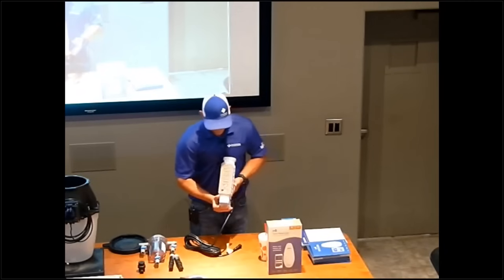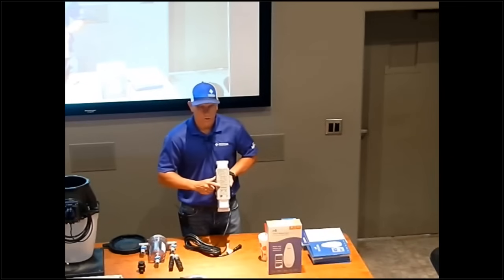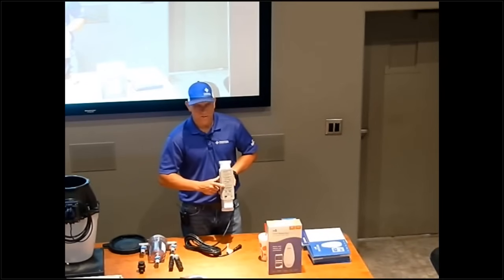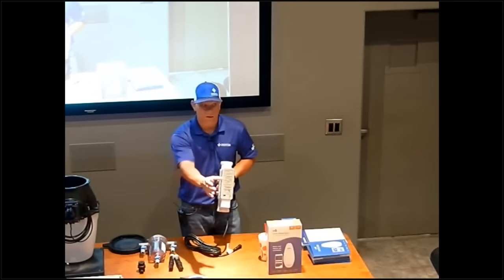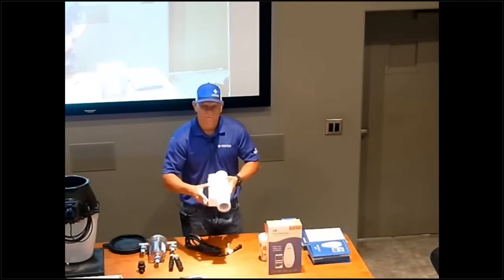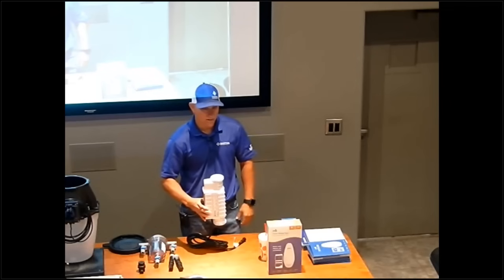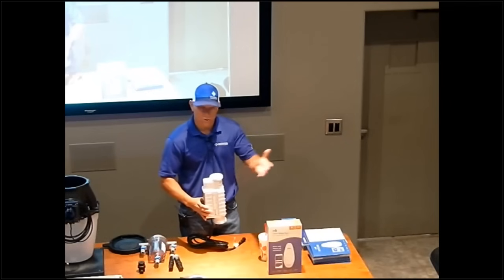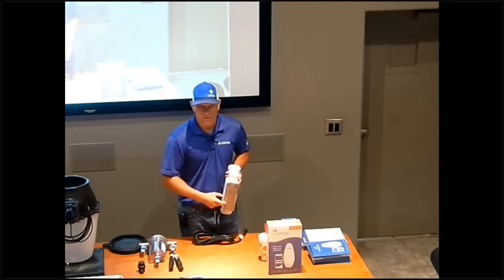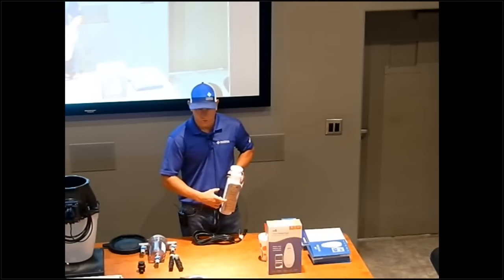You would know if it's wrong - you'll have a flow light that should be green, but it'll be red saying there's no flow. All I would do is turn the system off, pull the cell back out, flip it right side up or upside down, and put it back in line, then turn the pump back on. You should see a good flow, a green light.